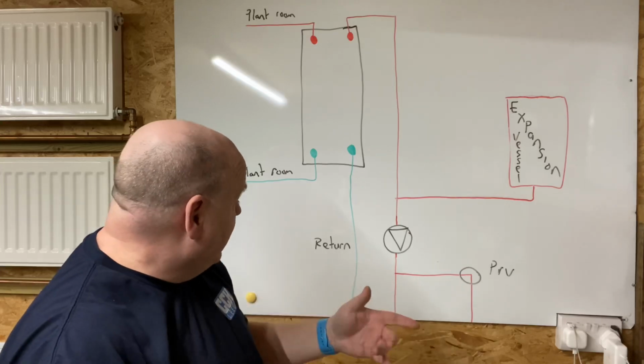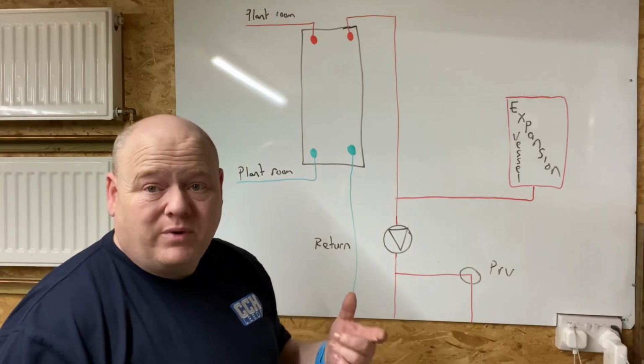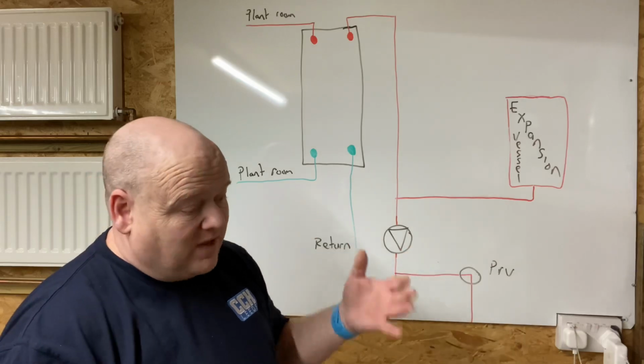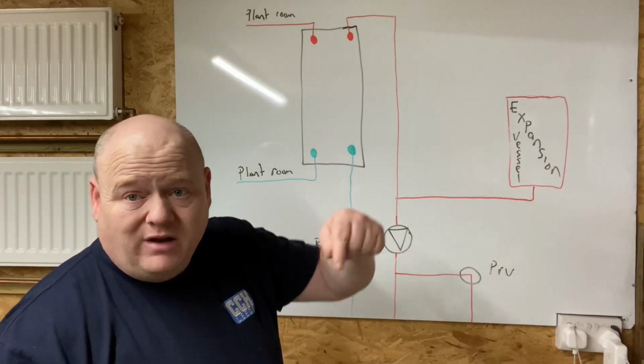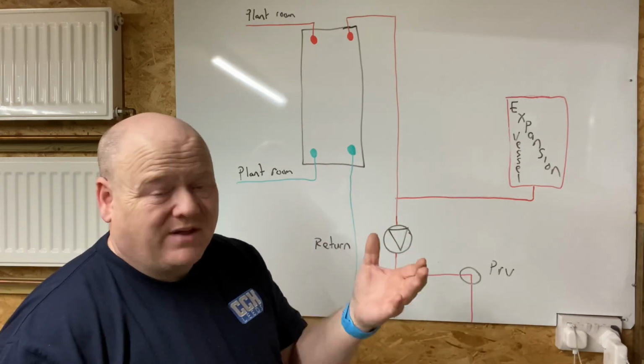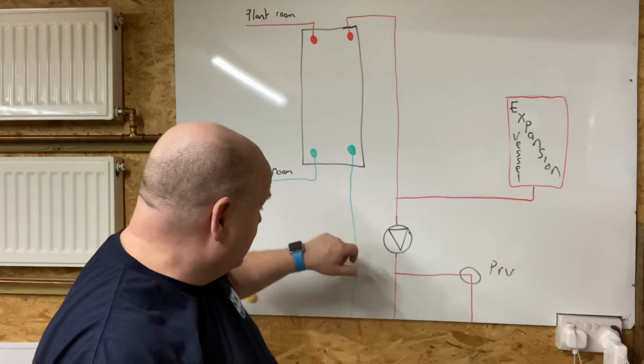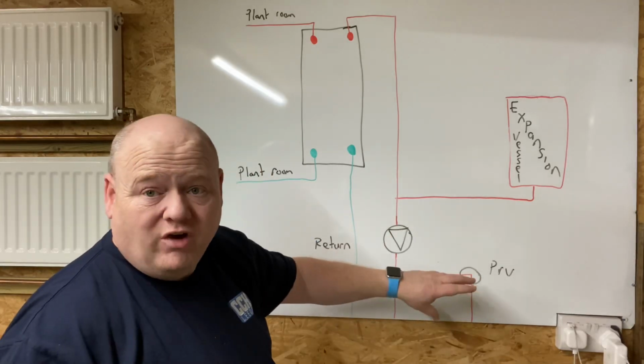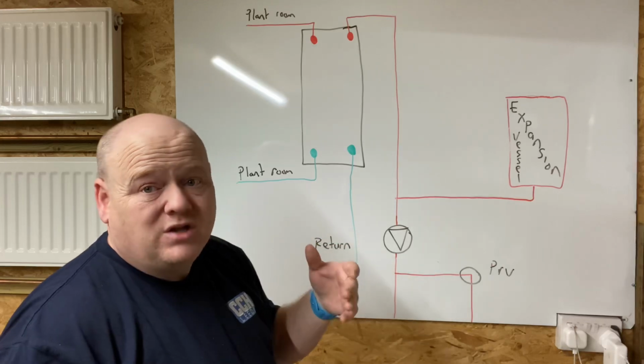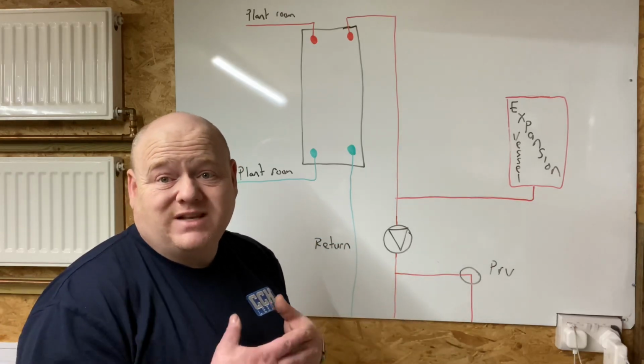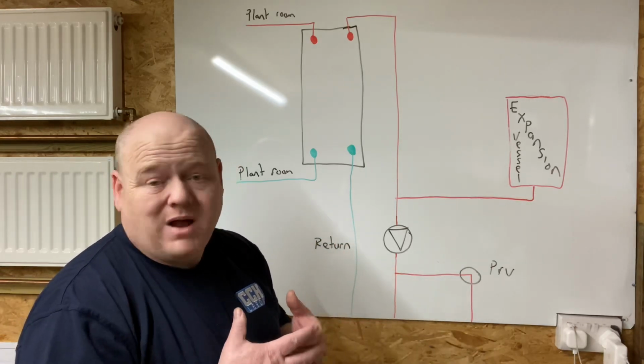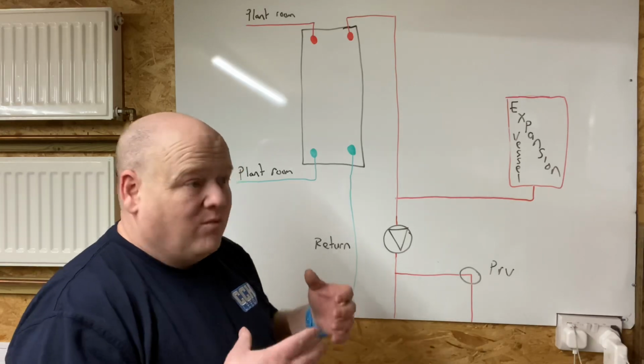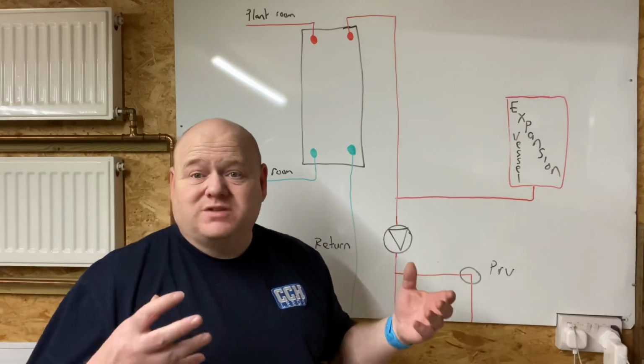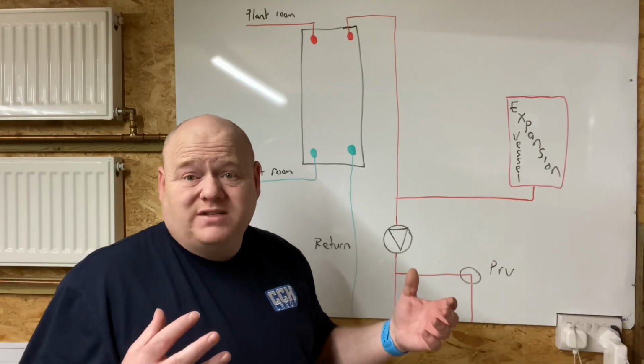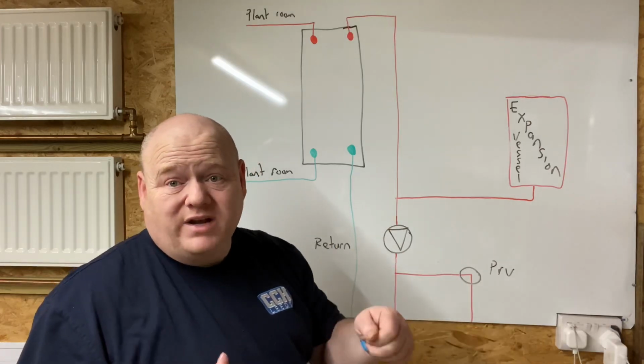The other thing you'd also need on this is a filling loop. And as David's shown, they had a built-in filling loop, so you'd have a filling loop similar to that. And what you'd do, you'd top it up as normal. There'll be a pressure gauge on. You'll top it up as normal to whatever pressure they say is the correct pressure. It might be 1 bar. And then once that's up to pressure, it's just the same as any other heating system where you can go around and bleed your radiators.